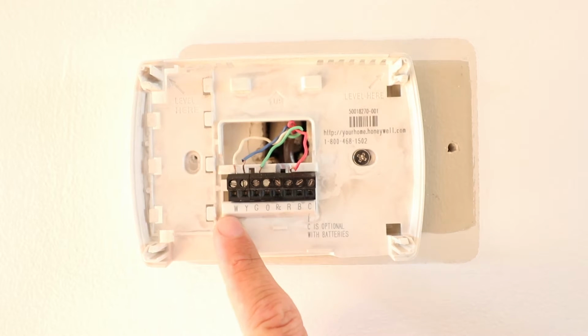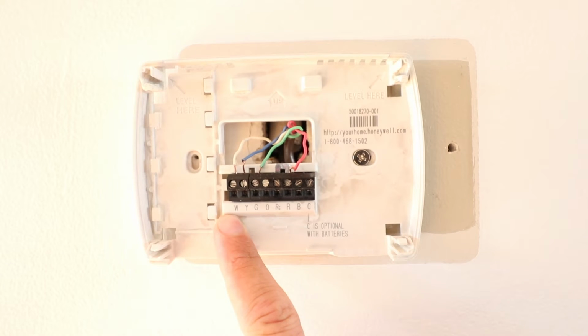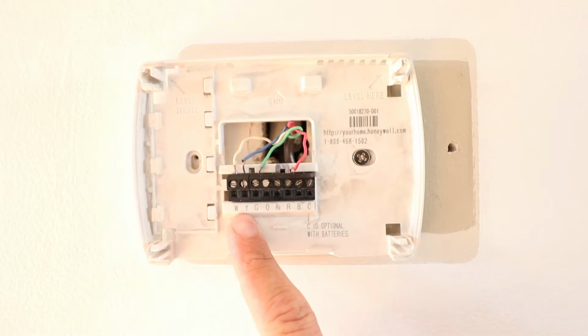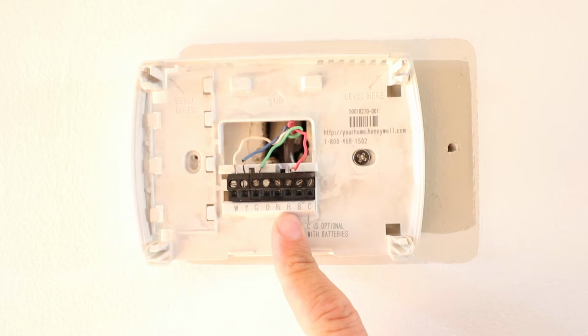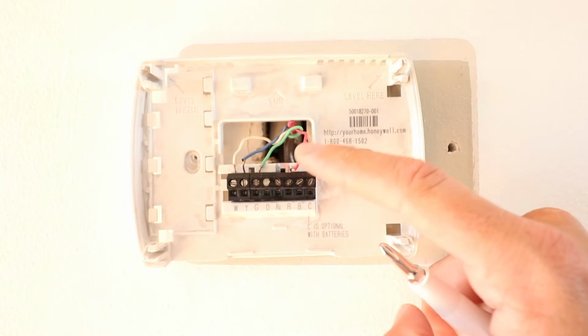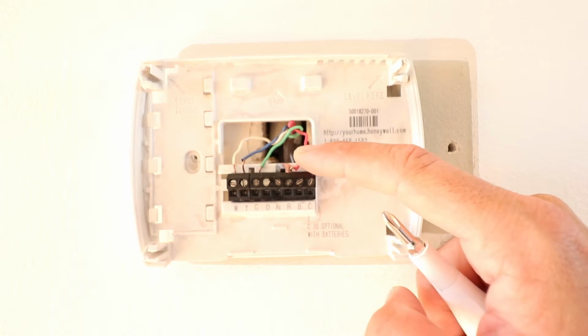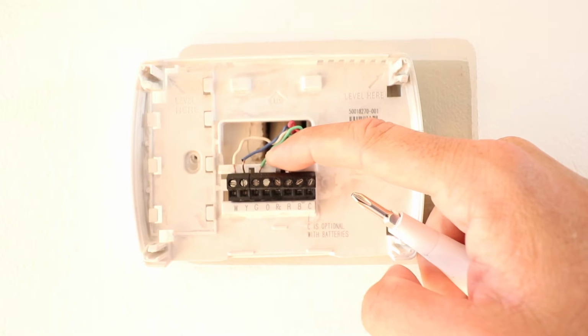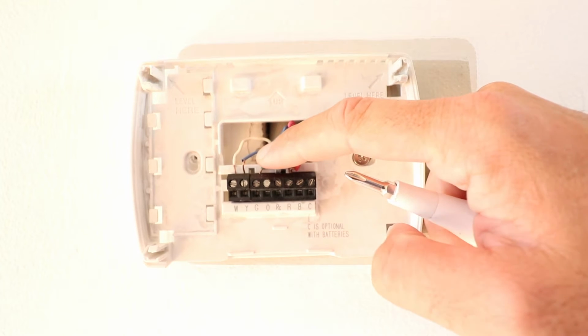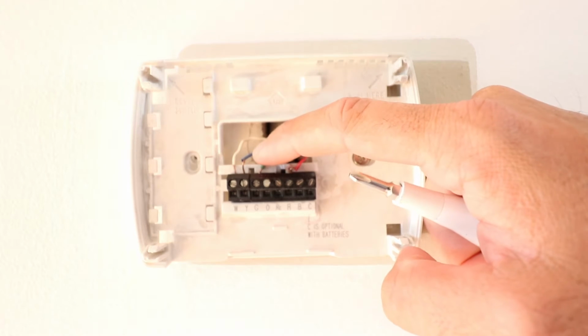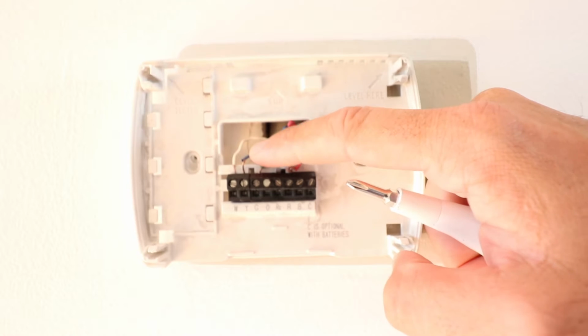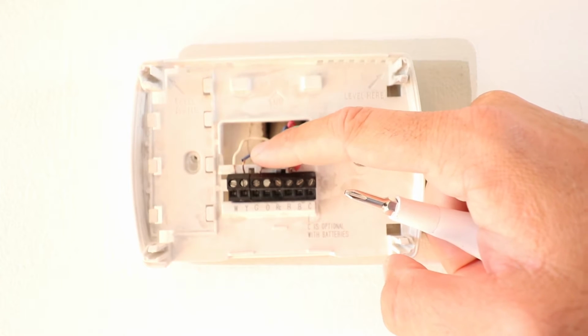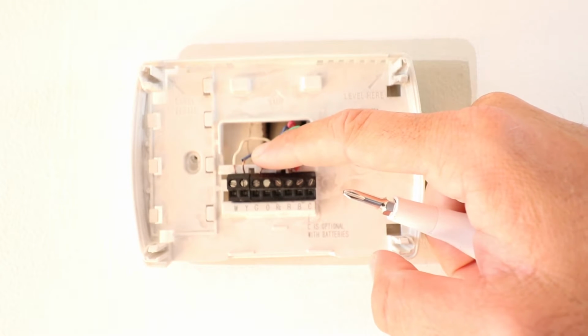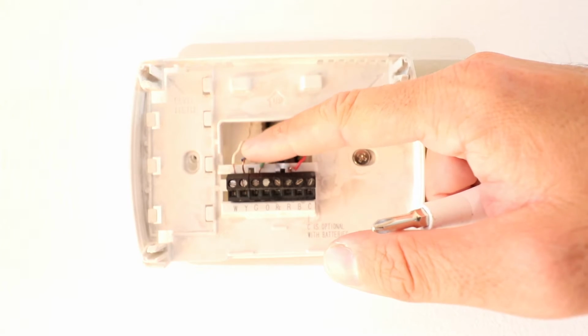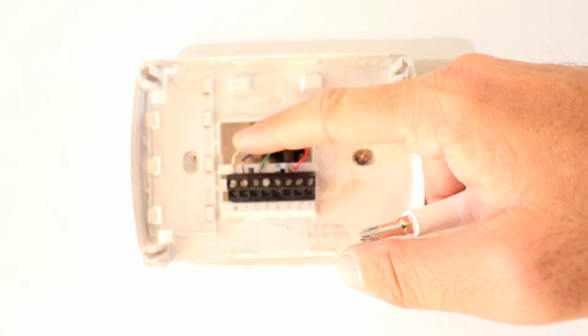We can see we have a W wire, which is white, a Y wire, which is blue, a G wire, which is green, and an R wire, which is red. The R wire is the power wire, the green wire is the fan wire, and the blue wire, in our case, is the air conditioner wire. Sometimes it may be yellow, but that's why it's important to take a picture so you know what wires go where. The white wire is the heating wire, or heating signal wire.